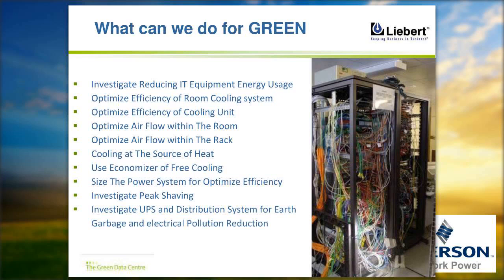Now, when you look at how we make our data center green, we have categorized various ways in which you can approach it. One is reducing the consumption of the IT equipment itself, because we believe that a saving of wattage at the source end, that is at the IT devices end, can give a big saving at the facility end. I will be describing this in my subsequent slide. There are a couple of other options which we have categorized here: improving efficiency through better cooling systems, and airflow management within the rack and within the room. How do we cool systems at the source end? There are a lot of options available here to make the data center green.